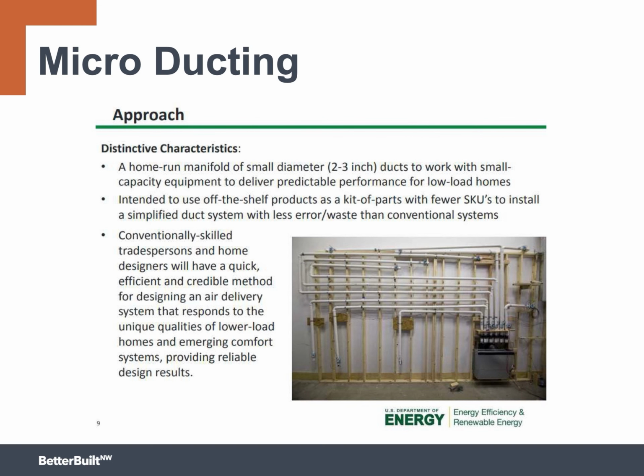This new microducting effort started around 5 or 6 years ago in partnership with the U.S. Department of Energy. The idea was to test this theory to see if the following could work. 1. Create a central manifold and then run multiple 3-inch ducts to each room. 2. Use as many off-the-shelf materials as possible. 3. Make it as simple as possible so that standard installers could easily be trained. This system is actually very similar to the PEX manifold water distribution system that we see in many homes today. A modern microducting system looks something like this. 2 to 4 3-inch ducts run to each bedroom. Each duct moves between 15 and 30 CFM of air.